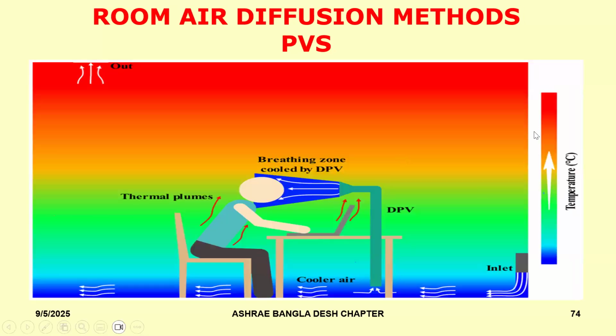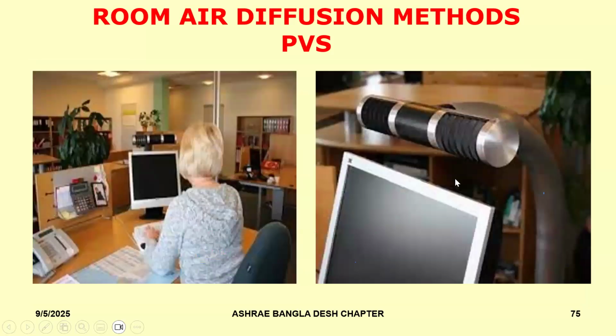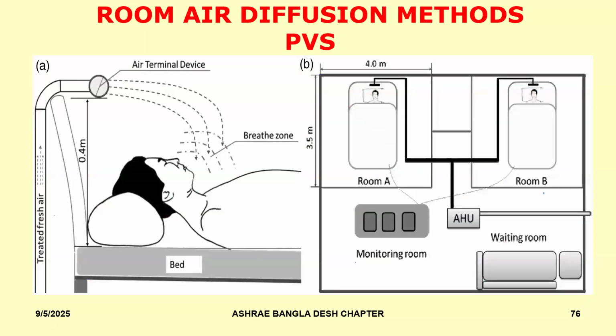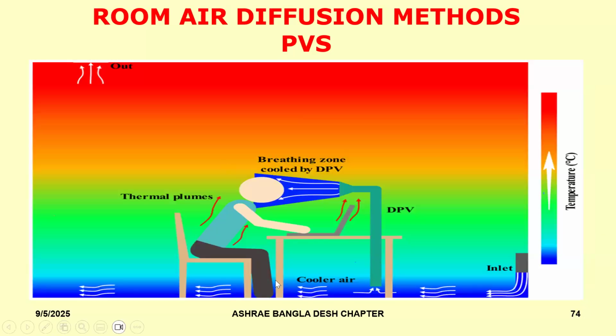Or you could have something like this, where you can have the underfloor, like what you just saw, and then this person's body heat, etc., is taken away by the thermal plumes, and the outdoor air is being brought directly into the breathing zone. So these things actually get built into the furniture. For example, like this, you see this lady here, she's got her console, she's working on it, and this is your personalized ventilation outlet. Nowadays, they are also talking about, for example, constructing this furniture in such a way that it could act as a radiant panel that can pick up the heat from the body, and then you get ventilated air coming directly into your breathing zone. So there are several methods of doing that.